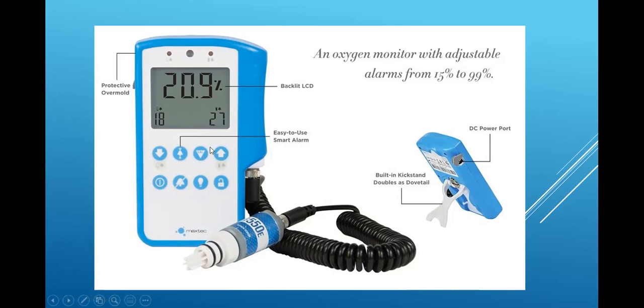So this is the oxygen analyzer here. See this button right here that says CAL? This is the calibration button, up and down. See, I can calibrate it. If it's in room air and that's showing 23%, that's too high. I need to push this down button, right, down to 21. Okay, and the same thing with 100%. All right. So this is one of the newer ones here.